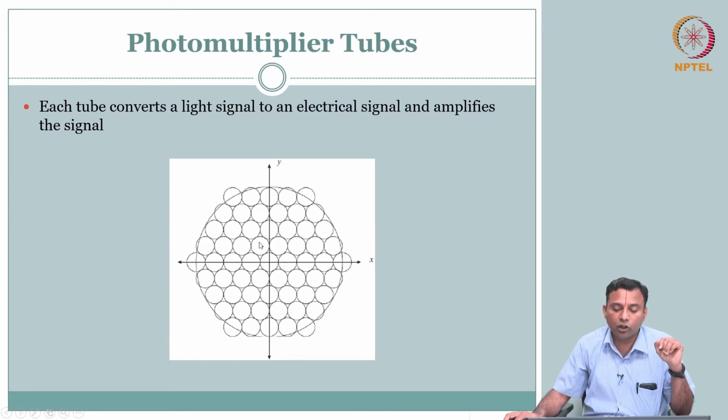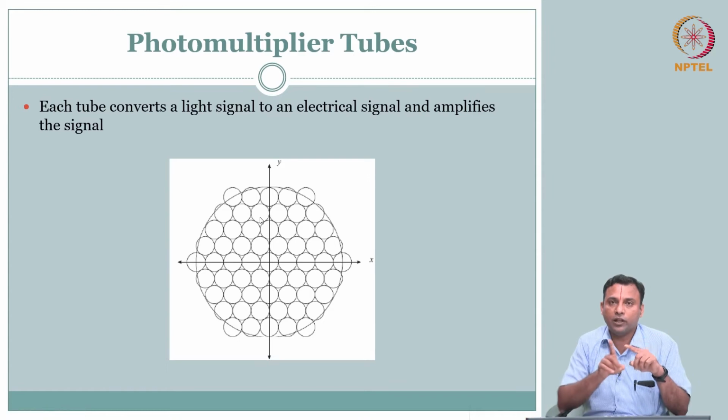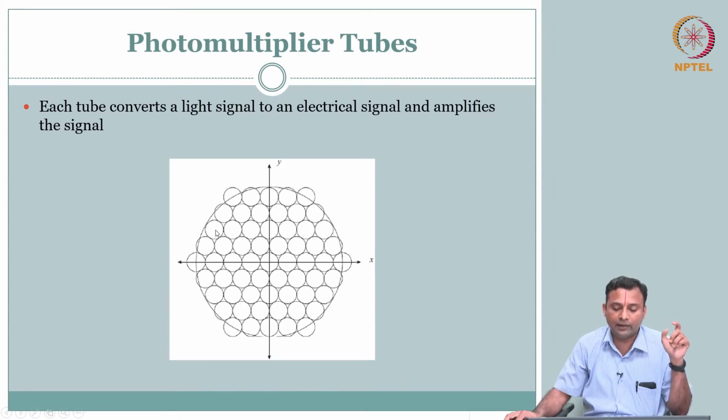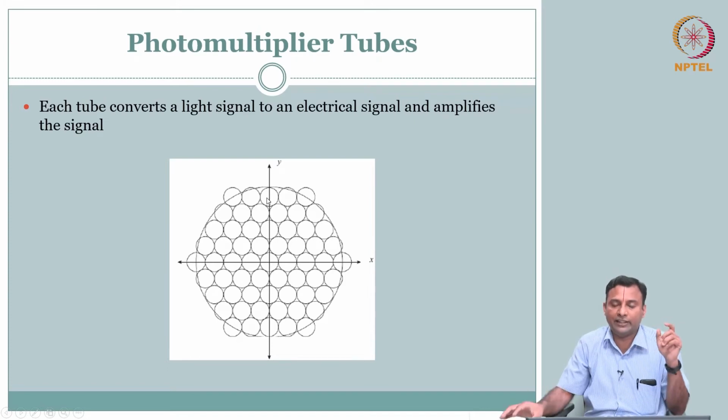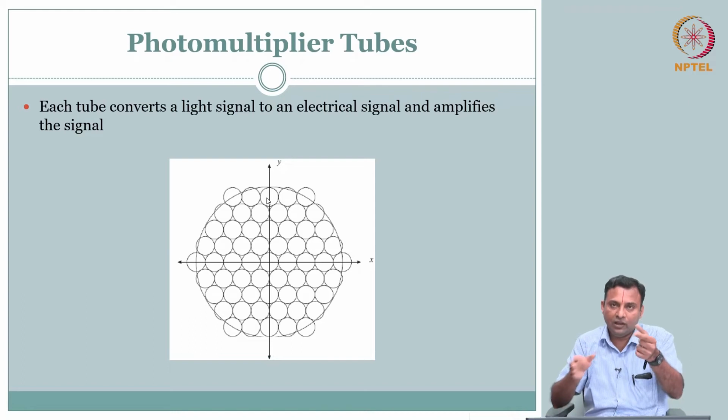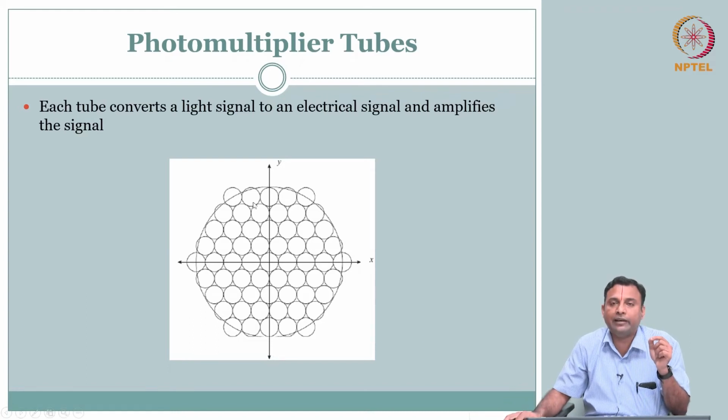Depending on the location where the light comes out, more of it will enter the nearest photomultiplier tube. The photons going to the side can enter the others as well, but the majority will enter along the line of sight, along the collimator. Out of the crystal it will enter the photomultiplier tube. The objective of the photomultiplier tube is to convert these light photons into an electrical quantity.